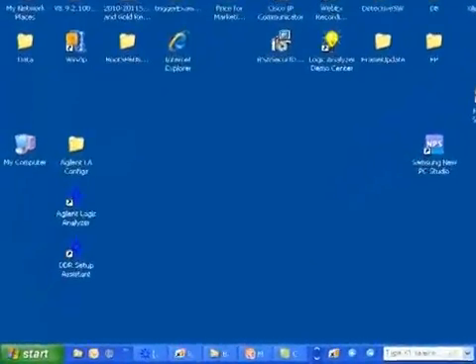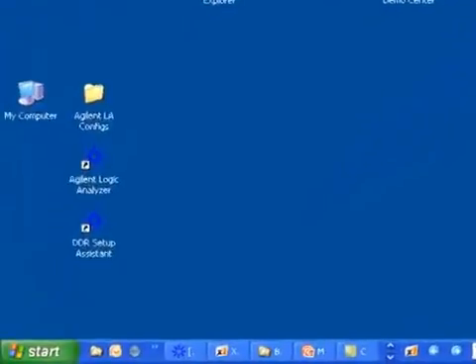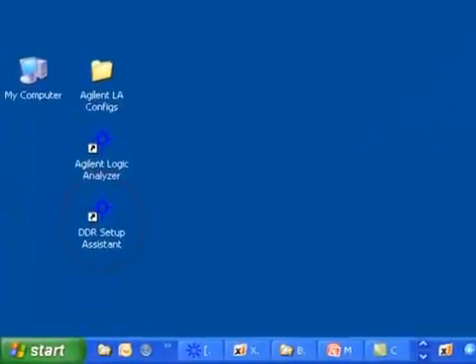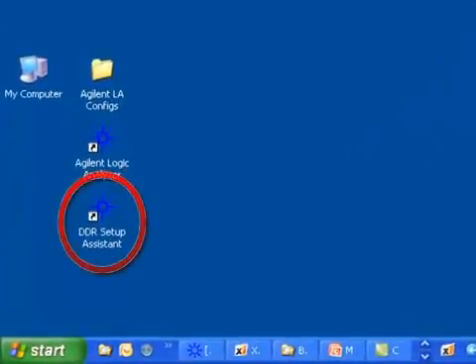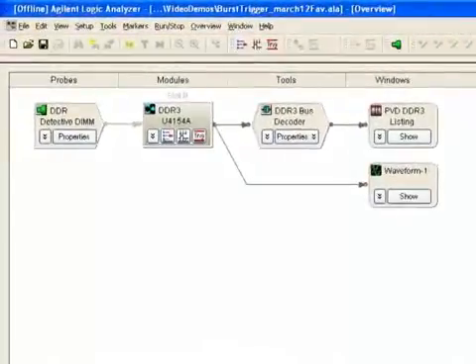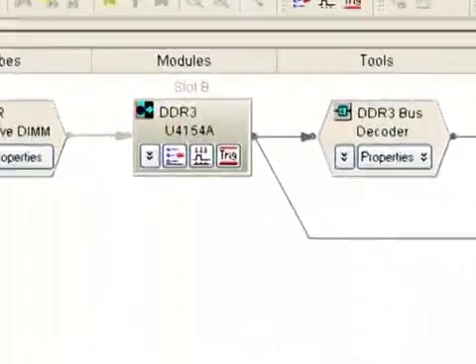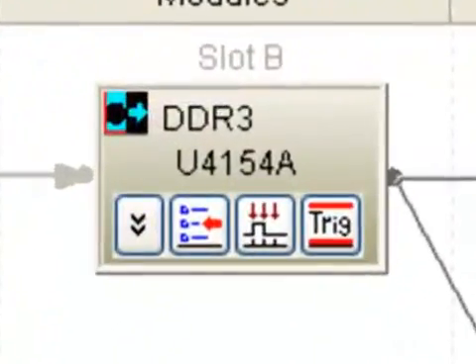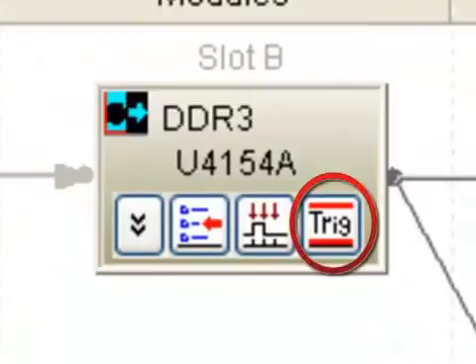Use the DDR Setup Assistant icon on your desktop to tune your U4154A system for state mode measurements before you start using burst triggering. To set up a burst trigger, open the trigger window from the U4154A icon.